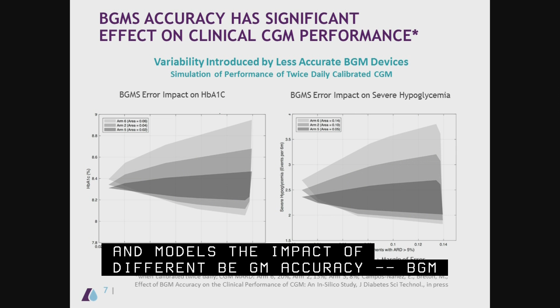Within each of these charts, the tightest cone shows the most accurate CGM sensor, with a MARD of 8, then 13%, and then a MARD of 20%. So the goal here is consistency. You want to keep the cone as narrow and as low as possible. The variable in this study is the margin of error of the blood glucose monitor used to calibrate the system, and that's what you see on the x-axis.